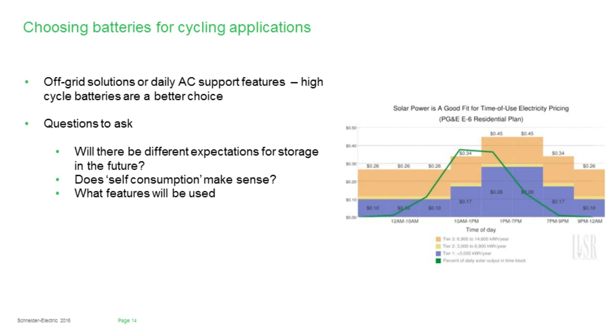We just don't get that control when we talk about AC coupling, because we don't necessarily have the ability to charge from a DC source. We're going to be buying power from an AC source to do charging, and depending on the jurisdiction, that can create some issues. So when we talk about what features are going to be used within the system, we have to make sure that we understand what the expectations are now and what they are going to be in 3 to 4 years. By the time you get to about 6 years with a cycling application, or cycling batteries sitting on float for that long, we're already starting to lose some of that capacity. So be sure that when you're deciding what the right storage solution is, you ask yourself what it is going to be like in 3 or 4, maybe 5 years. Does it make sense to bring in cycling batteries, or does it make sense to bring in some float life batteries and just have it as a backup solution?